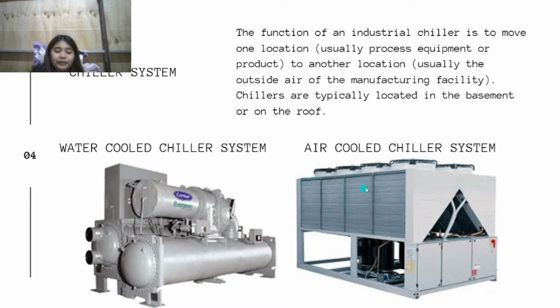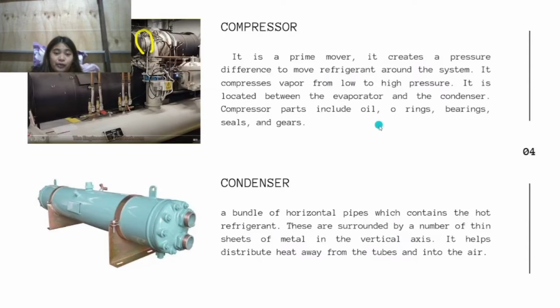There are two types of chiller system, a water-cooled chiller system and an air-cooled chiller system. The difference between the two is that an air-cooled chiller system is usually located externally, either up on the roof or at the ground level, and it does not use cooling towers; it dumps its heat into the ambient air. A water-cooled chiller system is typically located in the basement or lowest floor of a building. It needs a cooling tower to reject heat from the building. It produces chilled water and pushes this around the air handling unit and fan coil units. Both types serve the same function, which is to generate cold water for the air conditioning by removing the unwanted heat away from the building. So these are the different components of a chiller system.